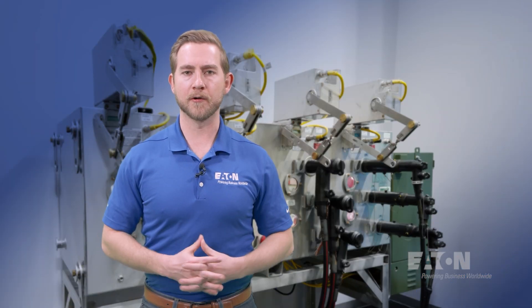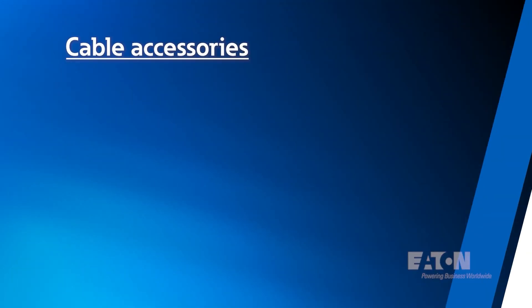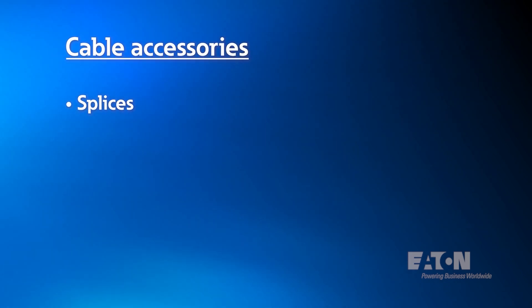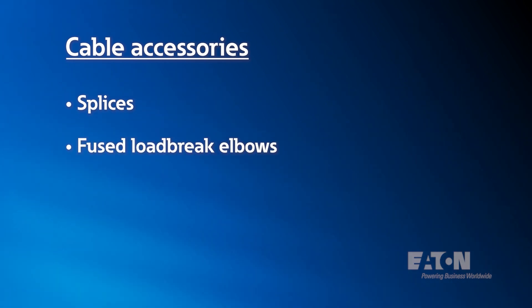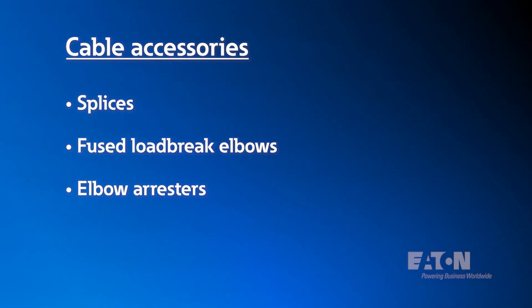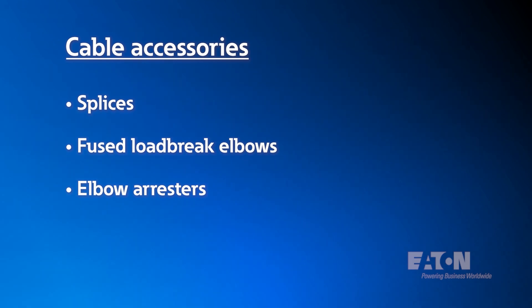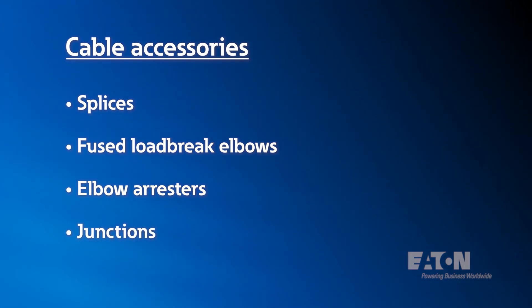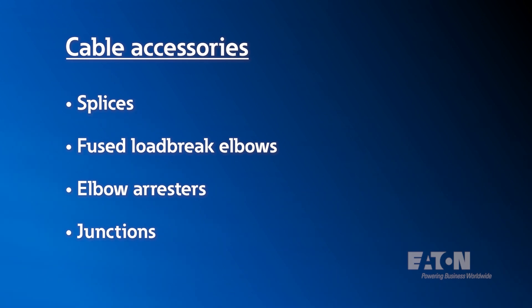As we mentioned before, cable accessories encompasses more than just load brake elbows and deadbreak T-bodies. It includes splices, which allow us to repair a cable or mate two or more sections of cable together. It includes fused load brake elbows and elbow arrestors. A utility may have an application for an elbow arrester where they can add an elbow arrester to a normally open point on a transformer and dramatically improve the surge protection. It also includes junctions, such as those we might find in a vault application, or feed-throughs, which we might find in a loop feed transformer configuration.